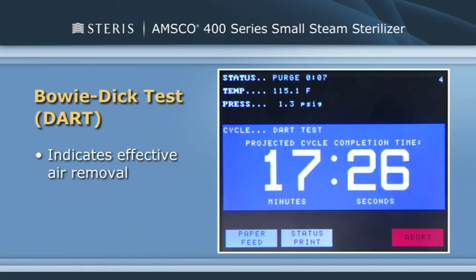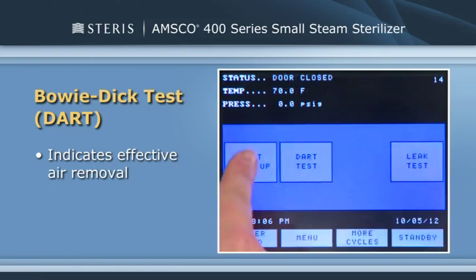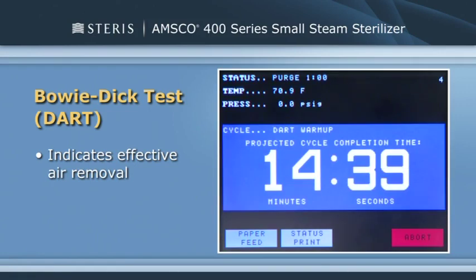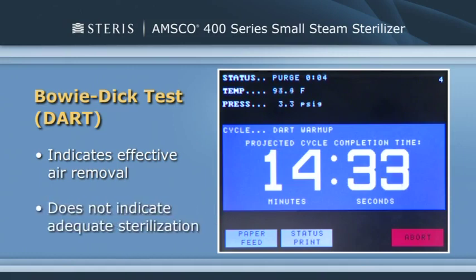This test should be run daily before processing any loads using a pre-vacuum cycle. To ensure valid test results, always run a warm-up cycle before performing a Bowie-Dick test to allow the machine to achieve proper operating temperature. It's important to note that the Bowie-Dick test is not a test for adequate sterilization. All test cycle values are pre-programmed and cannot be adjusted.